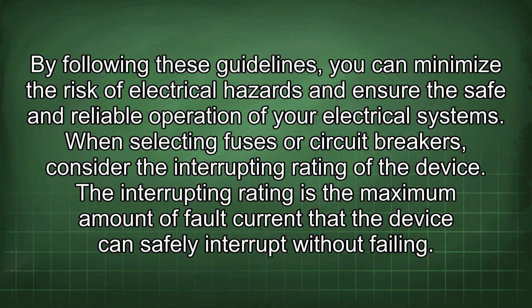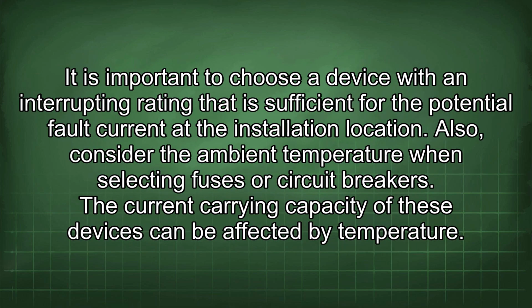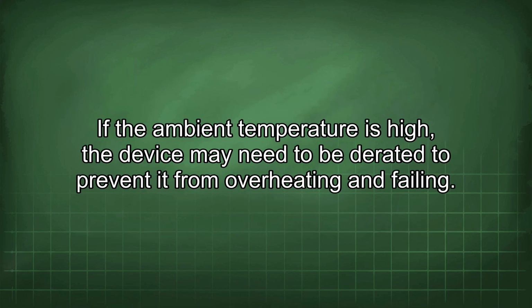The interrupting rating is the maximum amount of fault current that the device can safely interrupt without failing. It is important to choose a device with an interrupting rating that is sufficient for the potential fault current at the installation location. Also, consider the ambient temperature when selecting fuses or circuit breakers. The current carrying capacity of these devices can be affected by temperature. If the ambient temperature is high, the device may need to be derated to prevent it from overheating and failing.